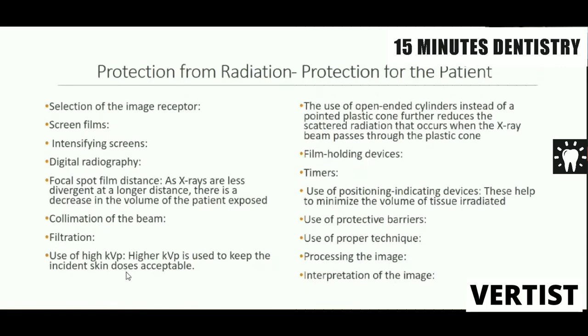The KVP and mA of the machine are important selection criteria. Cheap machines with lower KVP and mA will not give good diagnostic quality radiographs and will also have a shorter lifespan. Use open-ended cylinders, film holding devices, and electronic timers — modern timers work at 0.5 seconds compared to older spring-controlled timers measured in minutes. Use proper positioning indicating devices and protective barriers. Use a proper technique, process the image correctly, and interpret it properly. Taking a radiograph is not enough — if technique, processing, or interpretation is wrong, the entire exercise is wasted.